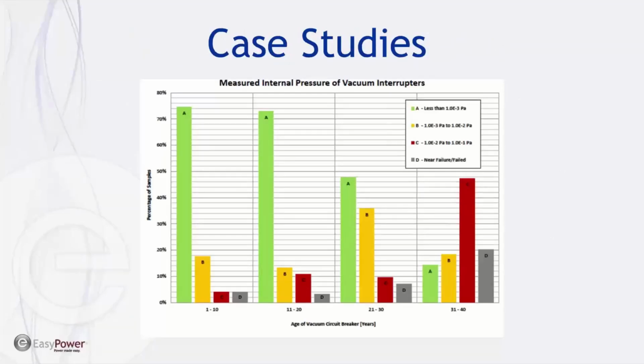So I have a few case studies of this MAC tester. And this graph is results from testing 300 of the circuit breakers that we have in stock at one of our affiliate companies, Circuit Breaker Sales. And what you see is they're divided into a few different categories, where green would be a good pressure or new pressure. B would be a midlife pressure. C would be approaching the point of failure, and D would be when it either fails our test or fails high pot test. And on the x-axis, you can see the age of the circuit breaker that were tested.